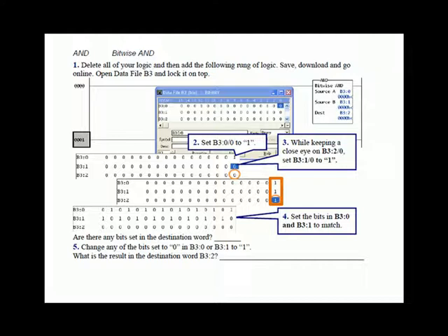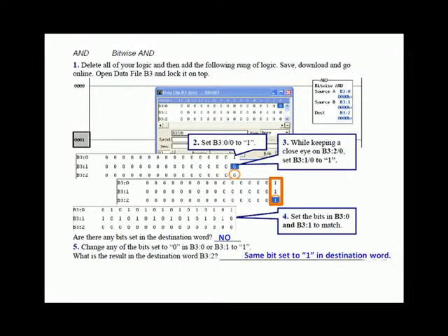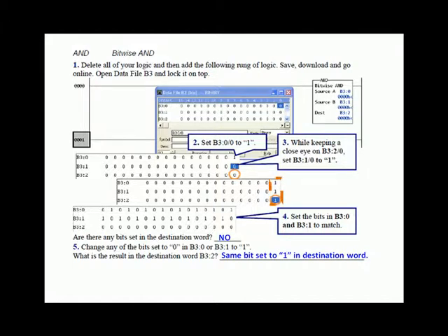I had you go through and set the bits in B3:1 so none of them matched the state of the equal position in B3:0. Then we asked: are there any bits set in the destination word, B3:2? No. Then I had you change any bits that are set to 0 in B3:0 or B3:1, but not both, to 1. The result was the same bit set to 1 in the destination word. So any bits in B3:0 or B3:1 set to 1 from this alternating pattern would make both bit positions equal to 1. 1 and 1 equals 1 in Boolean algebra.